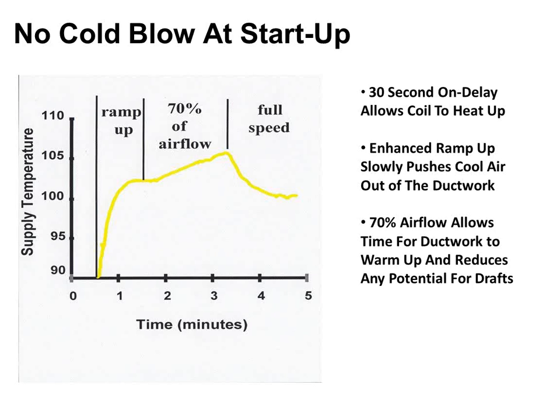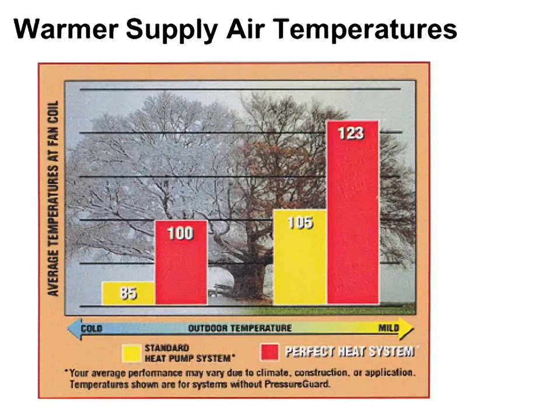So we'll have a ramp up period of basically a minute or so. In this case, on my drawing, it's a half a minute, where I don't even have the indoor fan running. I just leave it off completely, let the coil start warming up, right? And then when I turn the fan on, I'll have a variable speed indoor fan. And I should probably mention that if you're going to use variable speed compression, you're going to end up having variable speed outdoor fans and variable speed indoor fans to make it all work. So because I have a variable speed indoor fan, I'm able to ramp that up slowly and not bring it up on too much air until the temperature starts getting higher. Right, so because of those variable speed fans, I have the ability to mitigate that cold blow when it first starts up.